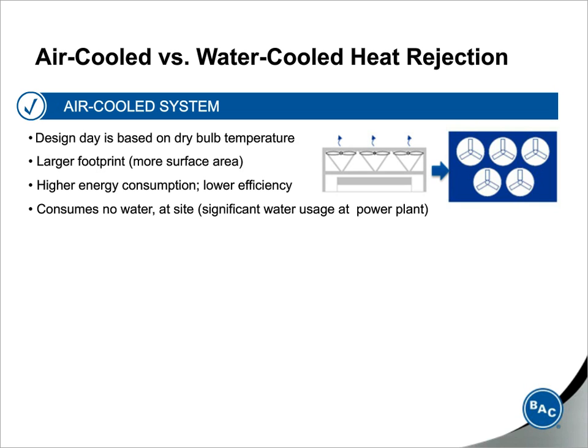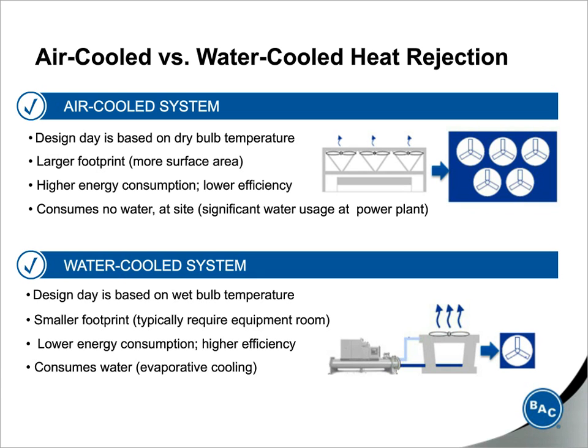Now, since water-cooled systems depend on the wet bulb temperature, which, again, can be several degrees lower than the dry bulb temperature, the outdoor footprint of the equipment is going to be much smaller, and energy usage is going to be much lower than on air-cooled systems.